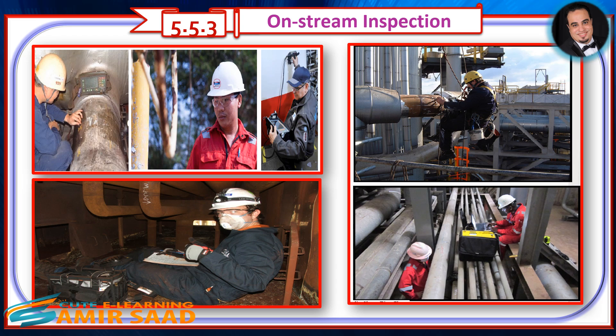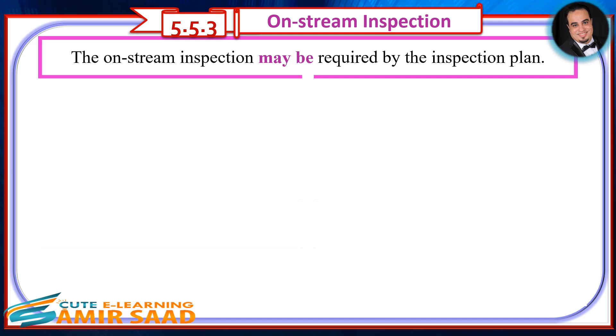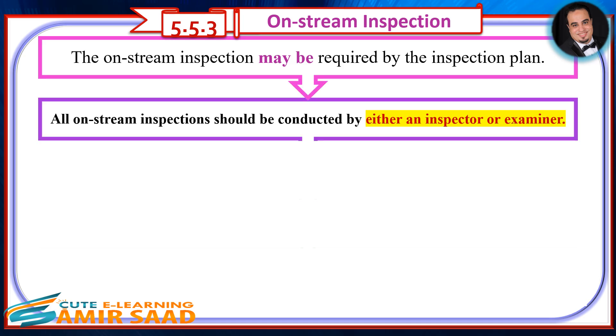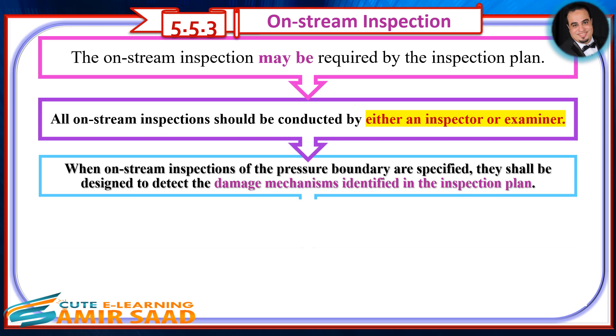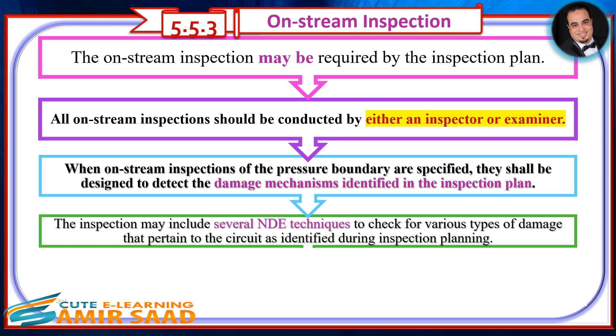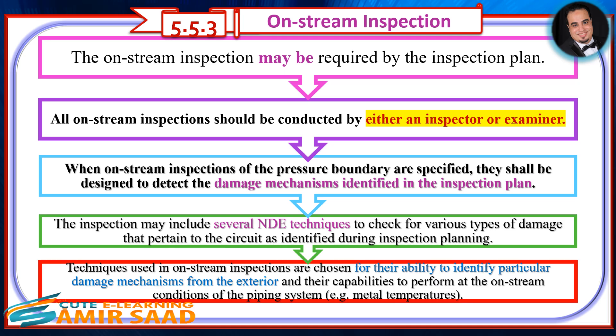The on-stream inspection may be required by the inspection plan. All on-stream inspections should be conducted by either an inspector or examiner. When on-stream inspections of the pressure boundary are specified, they shall be designed to detect the damage mechanisms identified in the inspection plan. The inspection may include several NDE techniques to check for various types of damage pertaining to the circuit. Techniques are chosen for their ability to identify particular damage mechanisms from the exterior and their capability to perform at on-stream conditions, for example metal temperatures.